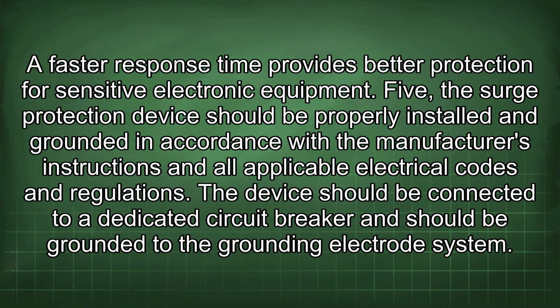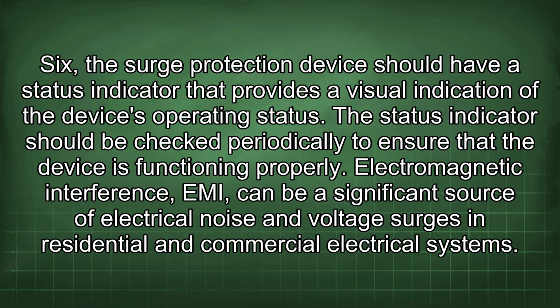5. The surge protection device should be properly installed and grounded in accordance with the manufacturer's instructions and all applicable electrical codes and regulations. The device should be connected to a dedicated circuit breaker and should be grounded to the grounding electrode system. 6. The surge protection device should have a status indicator that provides a visual indication of the device's operating status. The status indicator should be checked periodically to ensure that the device is functioning properly.